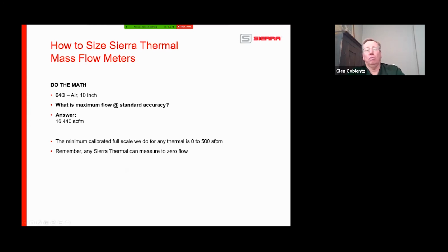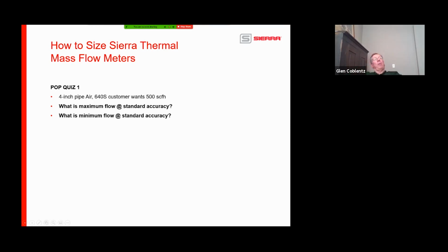All right. So now we're going to do a pop quiz or two. 4-inch pipe, air, 640S. Remember, at 640S, customer wants 500 standard cubic feet per hour. So what's the maximum flow at standard accuracy? What's the minimum flow? Maximum flow for air on a 640S would be what? What's the minimum flow? I need those two answers in the chat room when you can do it. And note, the proper answer will be in standard cubic feet per hour.